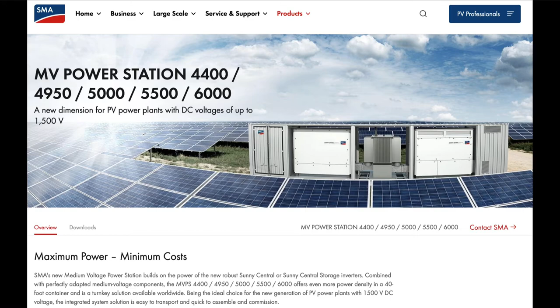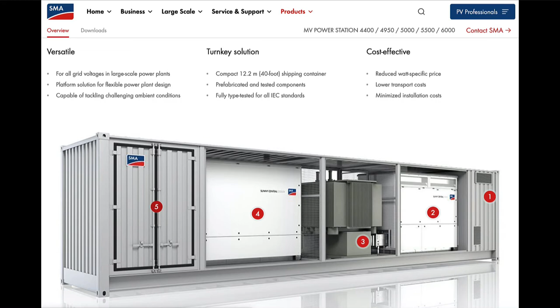So how many megawatts are you going to put on a transformer, paralleled into a medium voltage transformer? It's a really good question, and there's a lot of different arguments on what makes sense. Ultimately it comes down to cost, transformer costs and the like. We certainly see a lot of large transformers in large PV systems, so somebody's doing the math on that. But somewhere around 4 or 5 MVA would be the largest transformers you see.